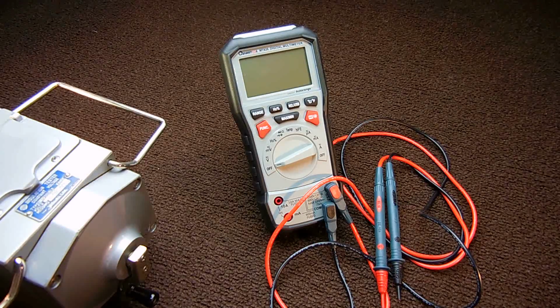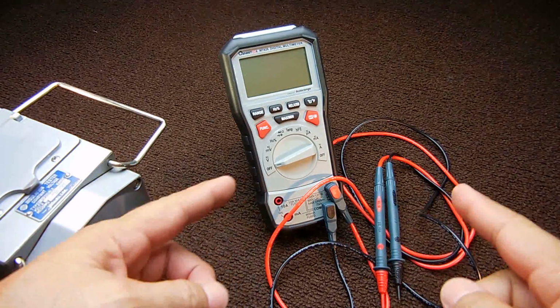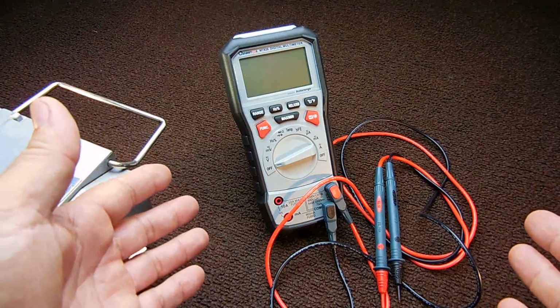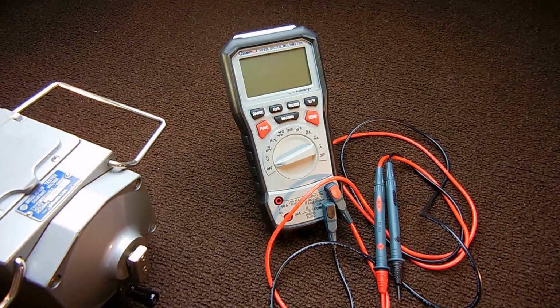And the easiest way to understand would be like a water pipe. If you have a water pipe and there's no pressure in that pipe or very little pressure, you're not going to notice any leaks on the outside of that pipe, even if the wall of that pipe is very, very thin in one spot. It may have a little tiny pinhole, or there's a fitting that's susceptible to leaking. You are not going to detect it. By applying water pressure to that same pipe, you're now going to be able to see that there's a problem with that pipe and that it leaks. So this is basically the same as a Megger. One is using water pressure, and in this case, we're talking about current leaking through a wire.